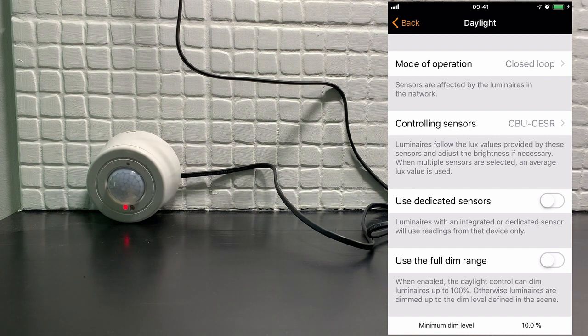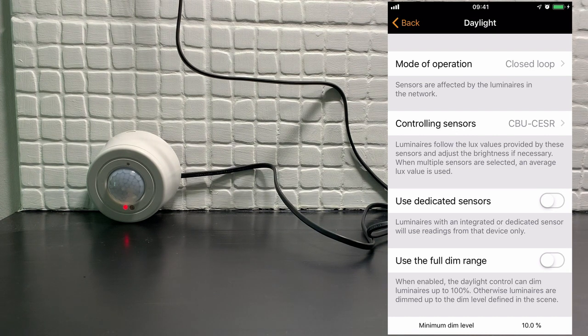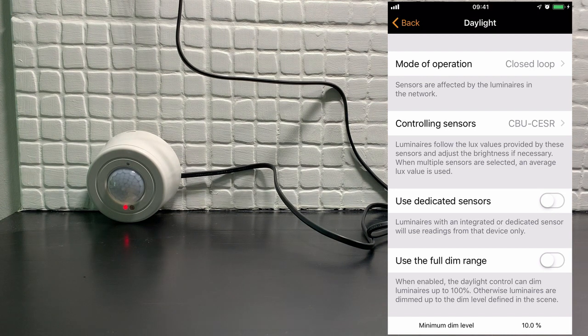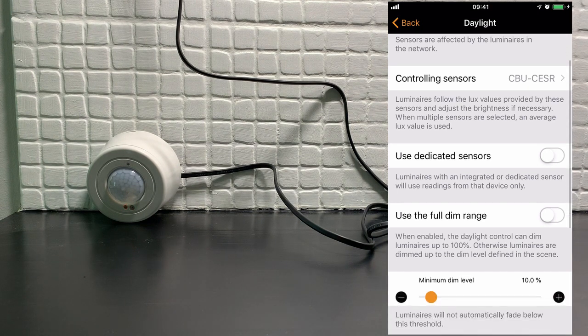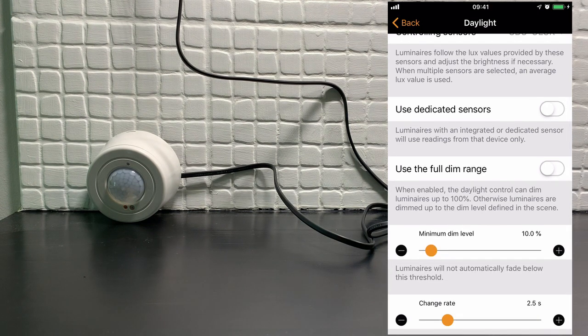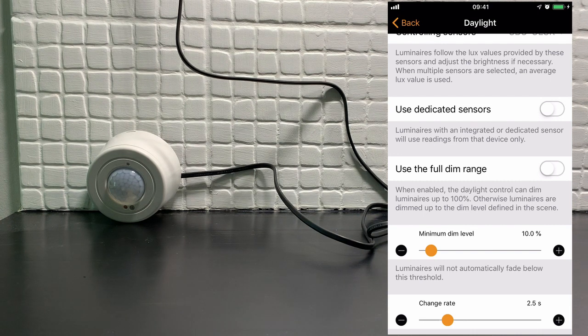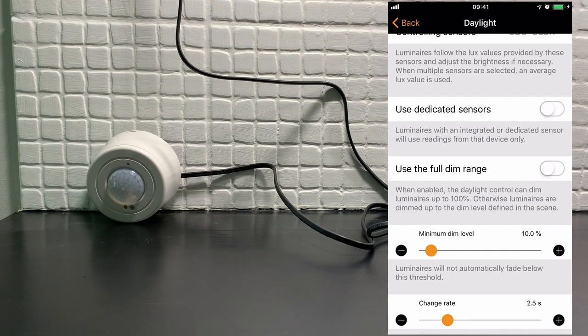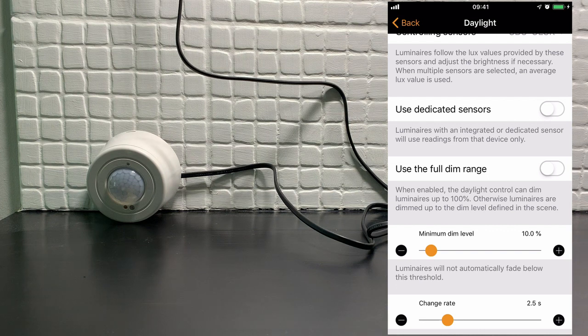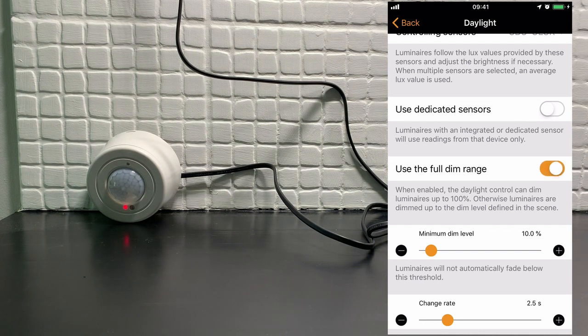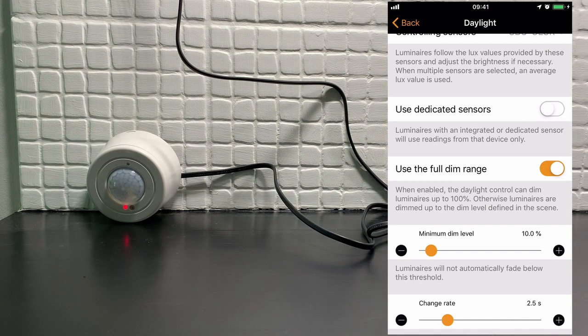We will not use the use dedicated sensor option, because that is for luminaires which actually have a built-in sensor. The option use full dim range will allow the scene to be dimmed beyond its maximum. So if I set a dimming level of 80% on the luminaire, this would allow it to go beyond that 80%.